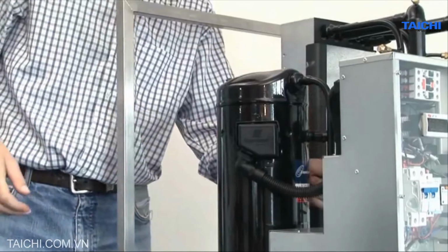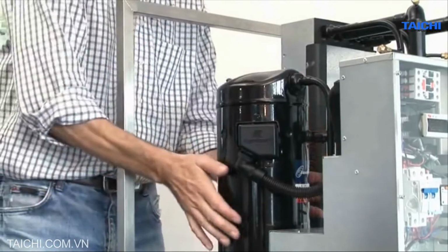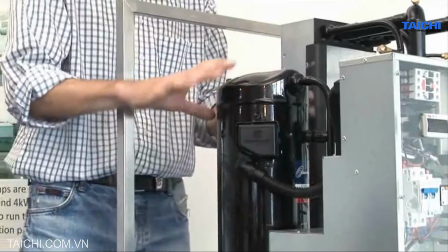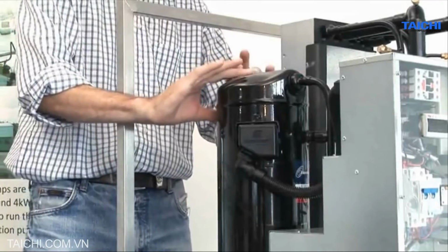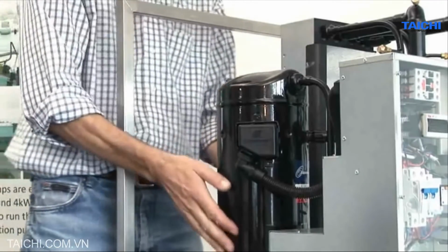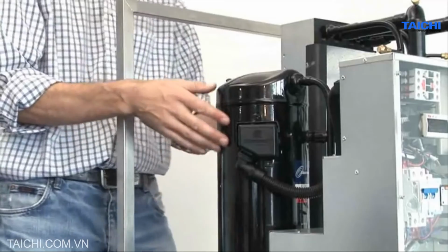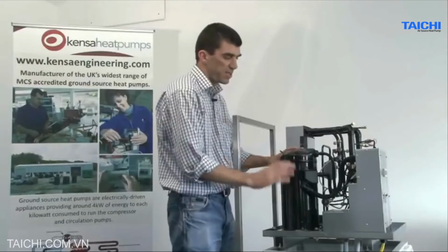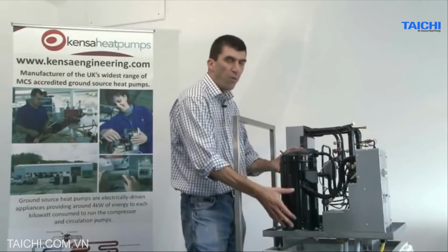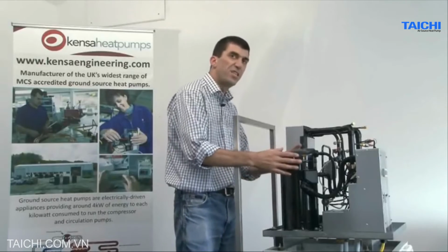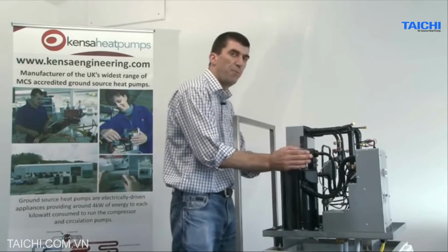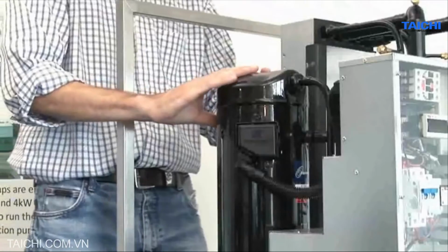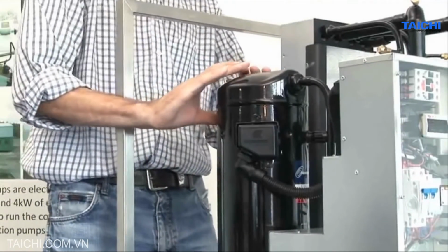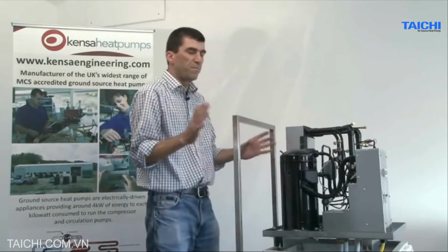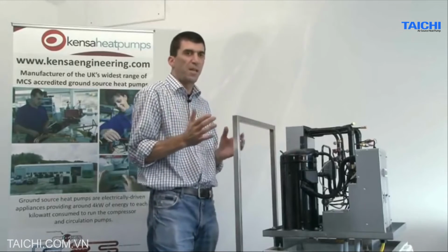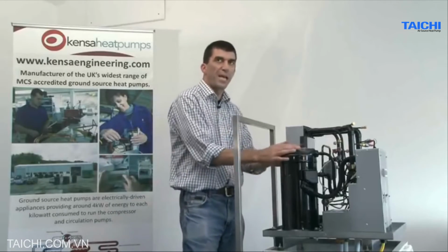So the gas is drawn back into the compressor, into the main body. By the time it reaches the scroll pump in the top, it's warmed up a little bit because it's absorbed the energy from the electric motor. It's warmed up a few degrees. So what we've done, we've picked up all the heat from the electric motor, so that energy isn't wasted, that becomes output energy. But the gas is still pretty cool at this point because it's low pressure. And probably the hardest thing for people to understand is, well, how does this cold gas become hot gas?